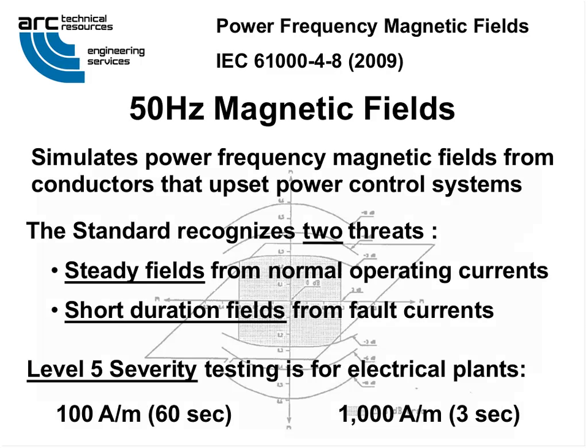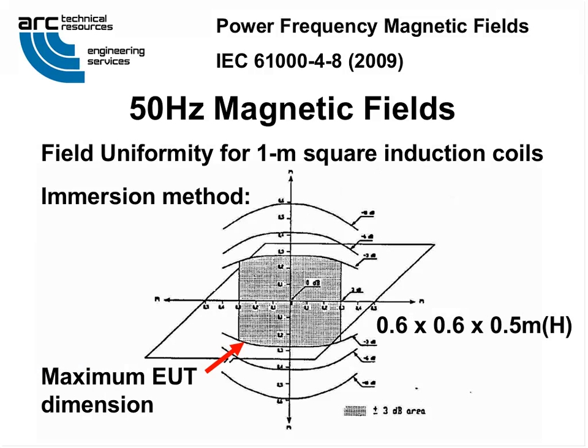That's 100 amps per meter for 1 minute, 1,000 amps per meter for 3 seconds. Drop that by a factor of 10 for outside the substation fence, 10 amps per meter for a minute, and 100 amps per meter for 3 seconds. Field uniformity for 1 meter square induction coils is given in this diagram. For the immersion method, the maximum EUT dimensions are 0.6 by 0.6 by 0.5 meters high. That's a common piece of rack mount equipment. If you make a common piece of racking equipment, you can use the standard 1 meter square induction coil.